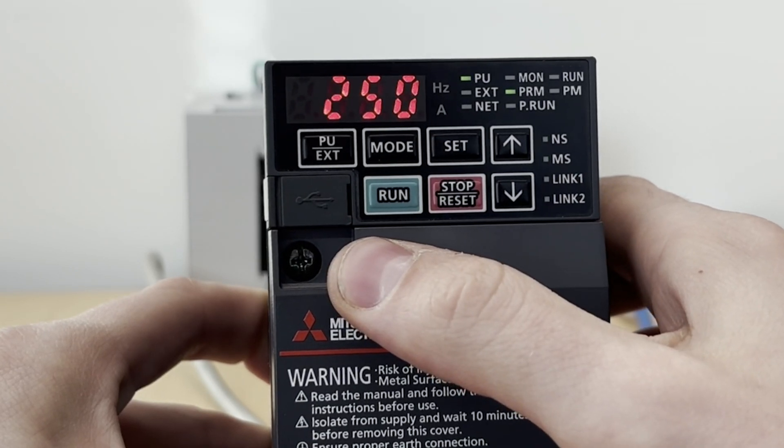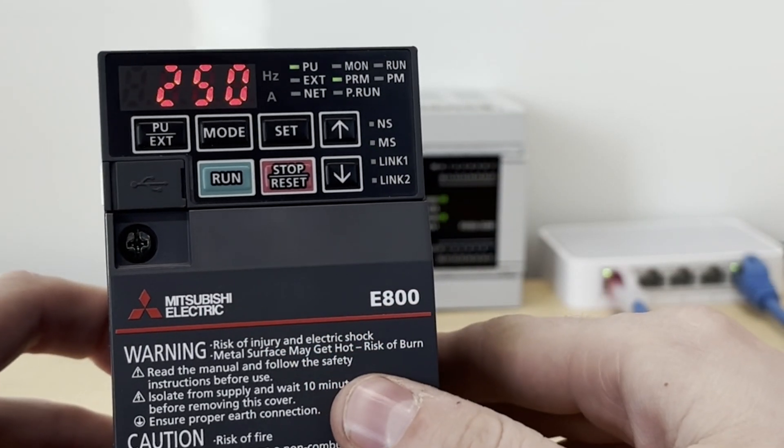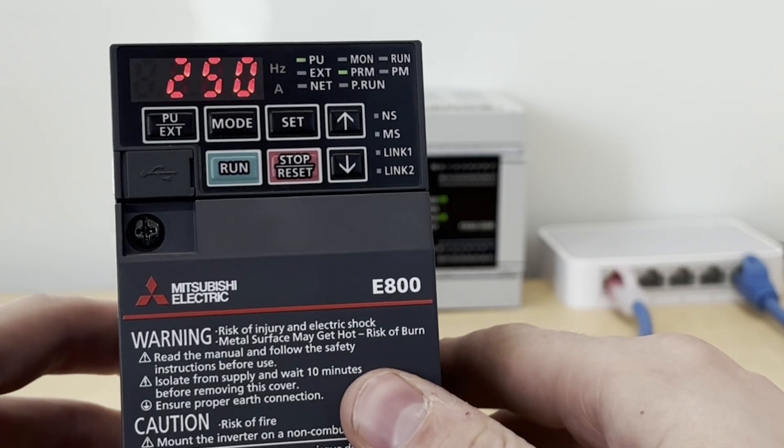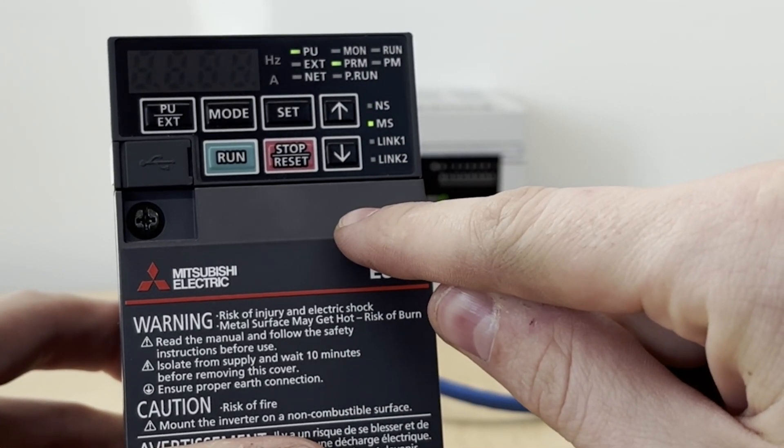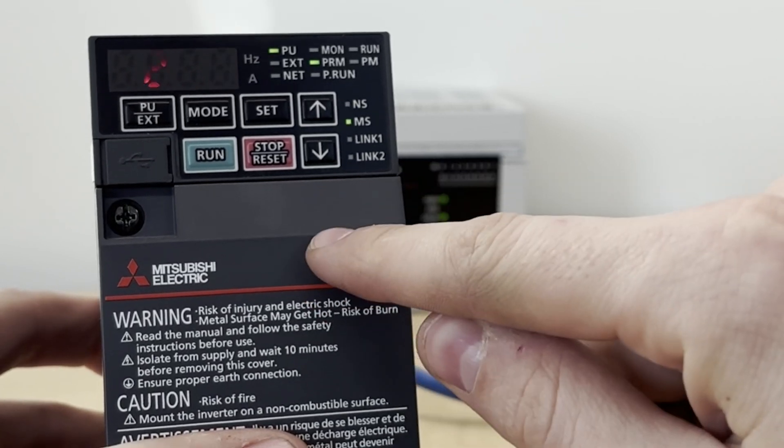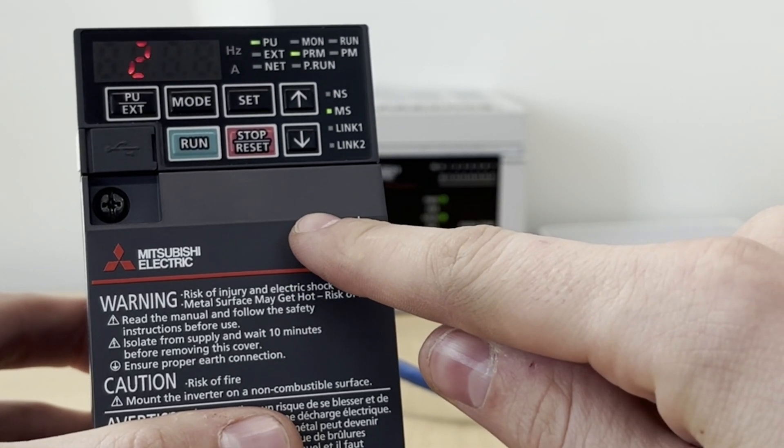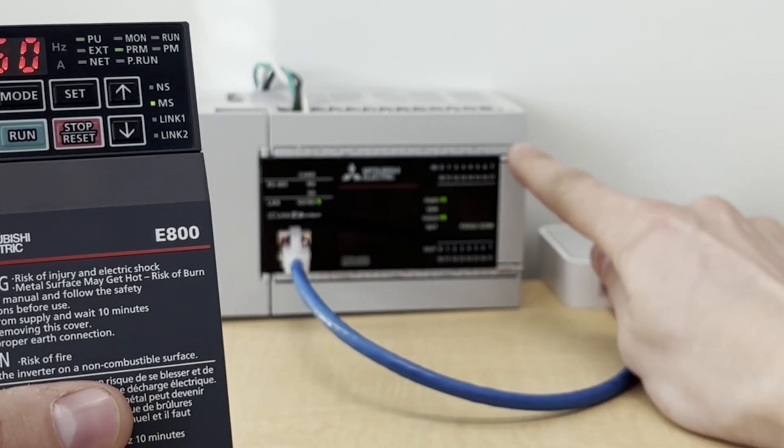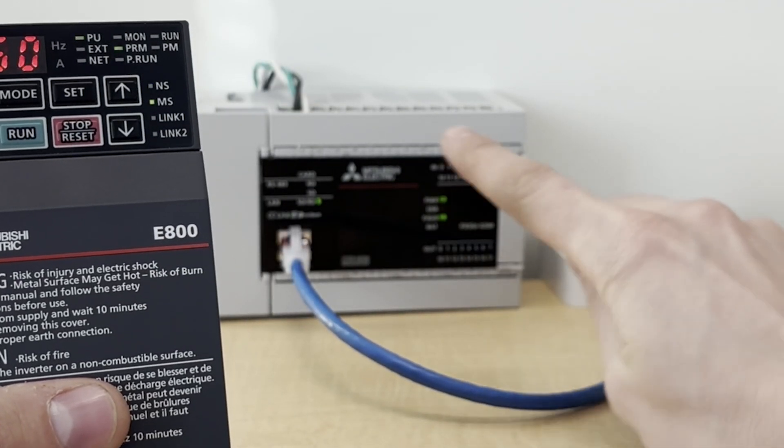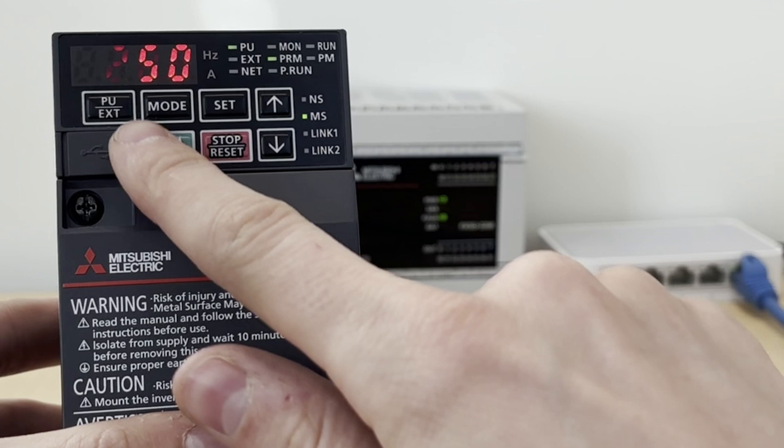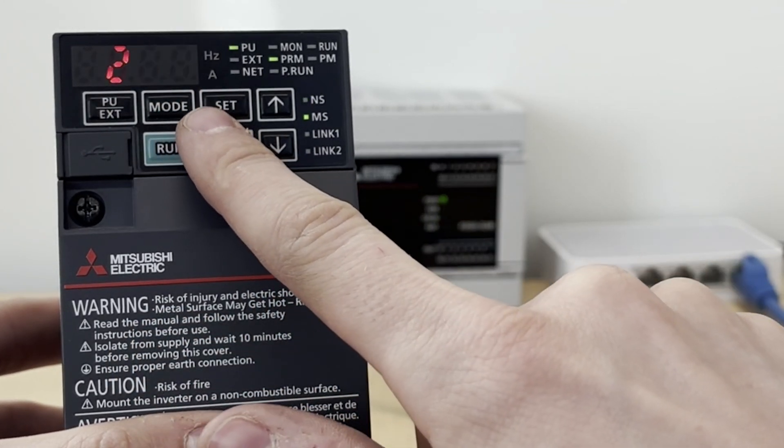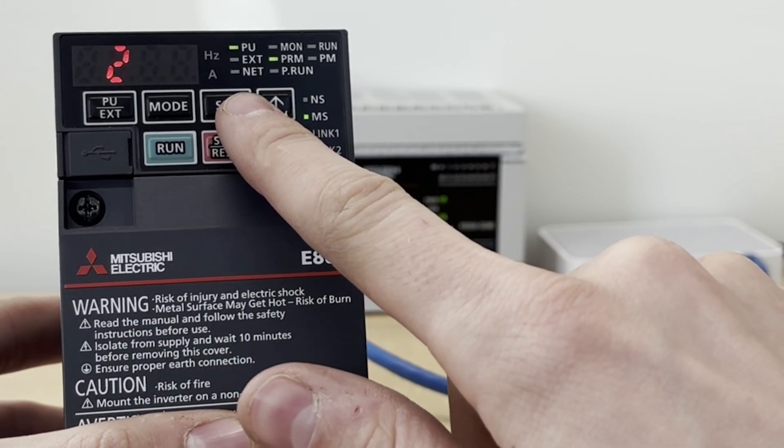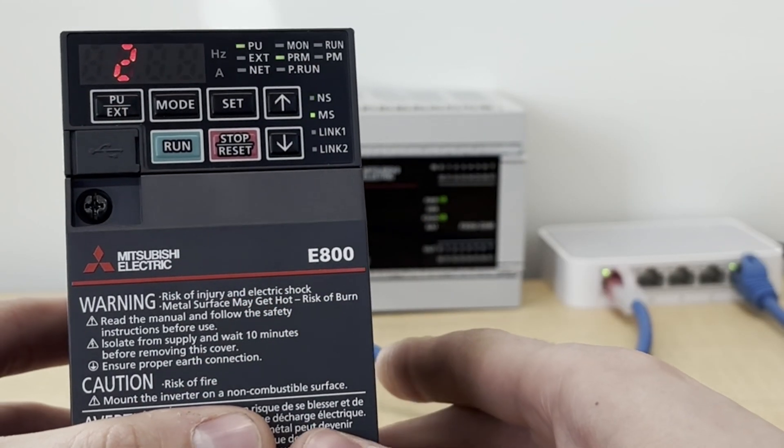Three, and then 250, which happens to be the default IP address of the FX5U CPU. Okay, our parameters are all set. We first set the communication mode of the inverter. We then set the IP address of the inverter, and then we set the Ethernet command source IP address, which is the same IP address as our FX5U CPU. The numbers look like they're cycling here. I think that's just an effect of my camera's frame rate. This is supposed to be solid.